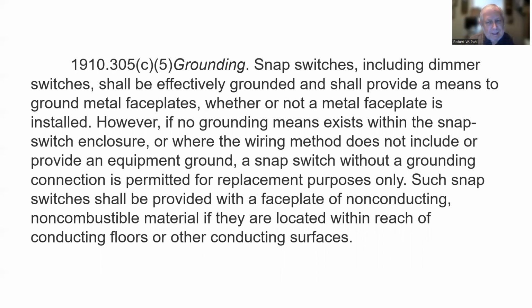However, if no grounding means exists within the snap switch enclosure, or where the wiring method does not include or provide an equipment ground, a snap switch without a grounding connection is permitted for replacement purposes only. Such snap switches shall be provided with a faceplate of non-conducting, non-combustible material if they are located within reach of conducting floors and other conducting surfaces.